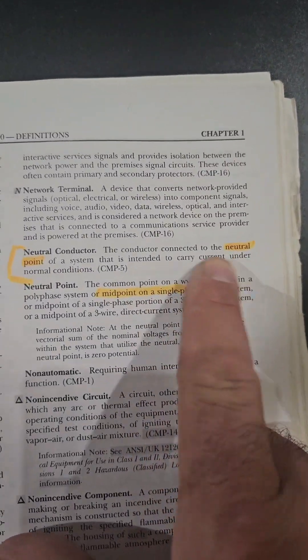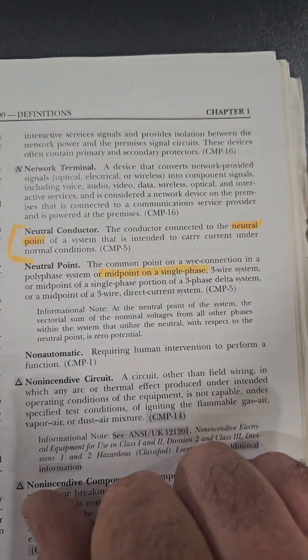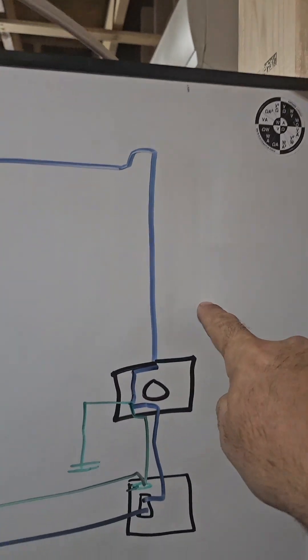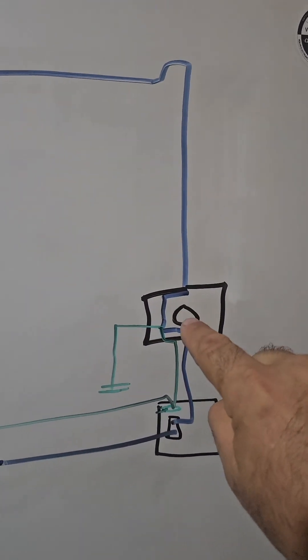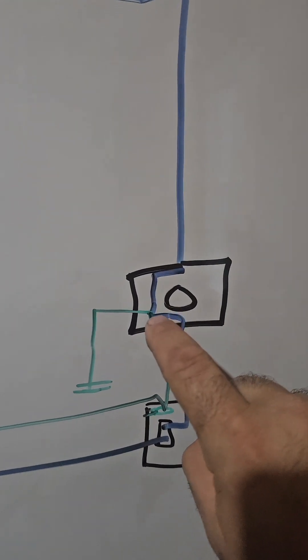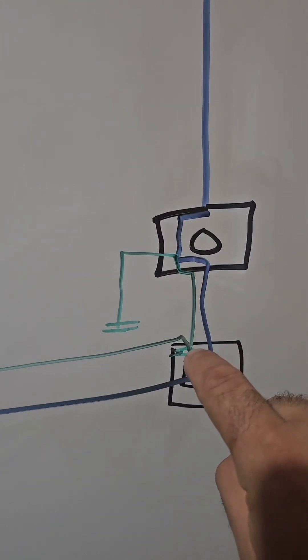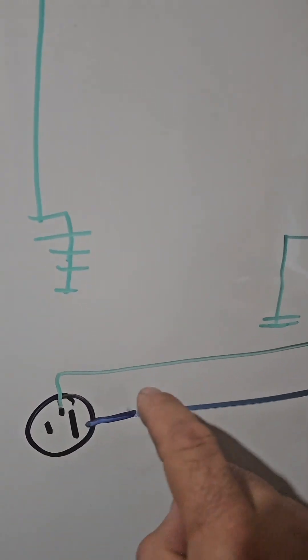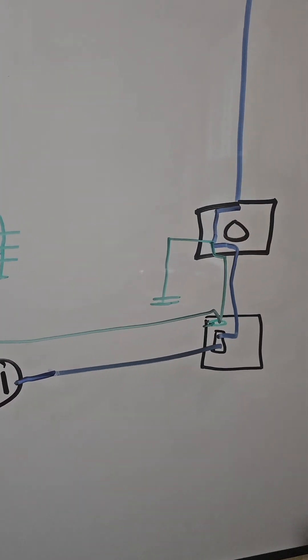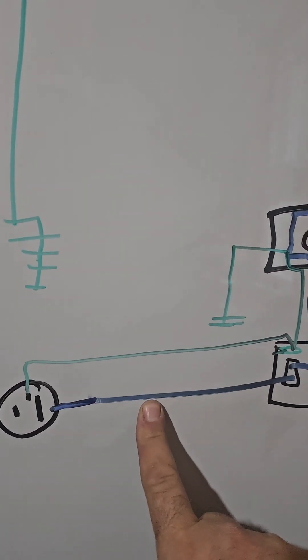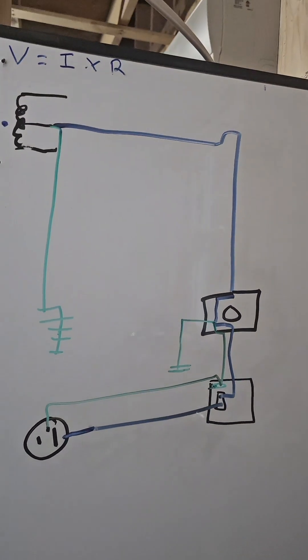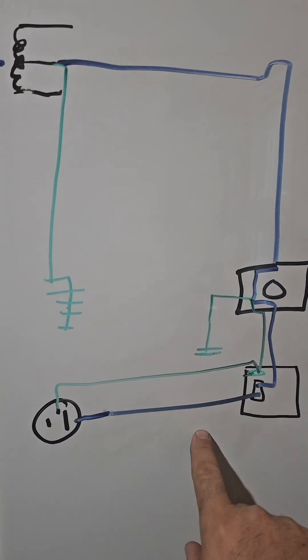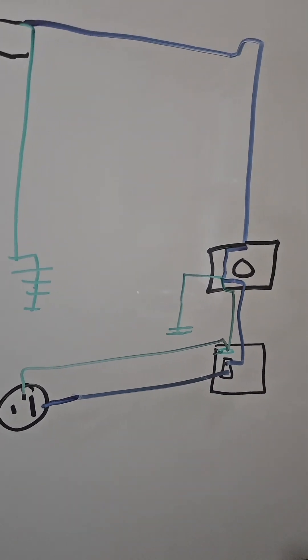Why does it say 'intended to carry current under normal conditions'? Because we have a second conductor that also connects to the midpoint. Here is where we split and our grounds and neutrals become separate. The green or bare wire is bonded to the can of the panel and goes to the third prong. Both wires are grounded and connected to the midpoint, but the neutral is the one we intentionally put current on. That is why I think this fits the definition of both a neutral and a grounded conductor — it is grounded, connected to the midpoint, and intended to carry current under normal conditions.